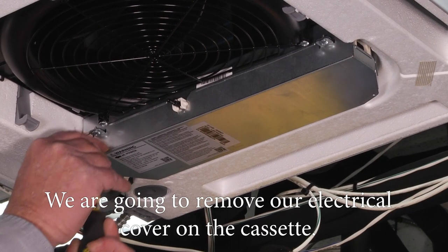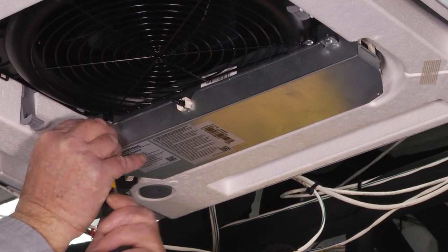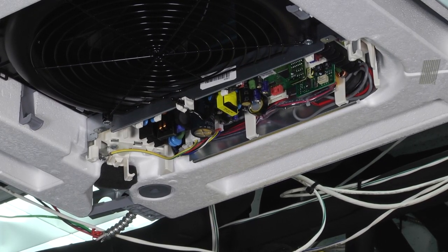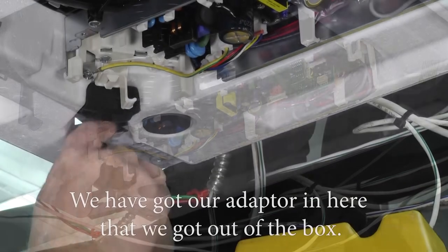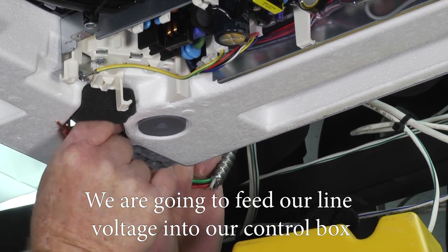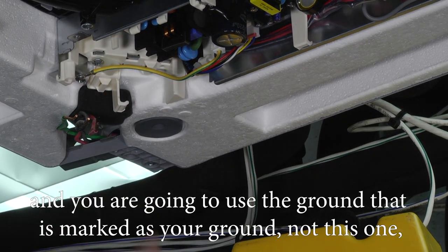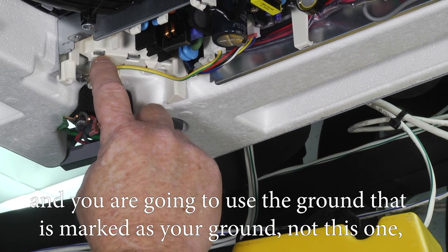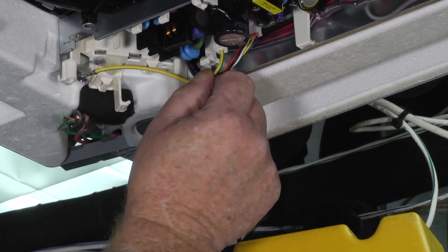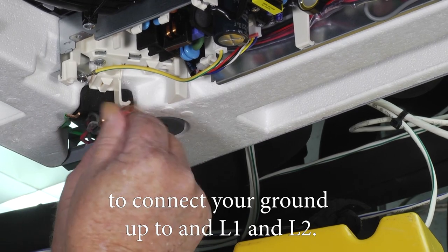Now we're going to do our electrical. We're going to remove our electrical cover on the cassette. There's two screws to give you access to your control wiring. We've got our adapter that we got out of the box. We're going to feed our line voltage into our control box and that's going to connect to your L1, L2, and you're going to use the ground that's marked as your ground, not this one. This is the ground for our control box. Make sure you use the other grounding screw to connect your ground up to L1 and L2.